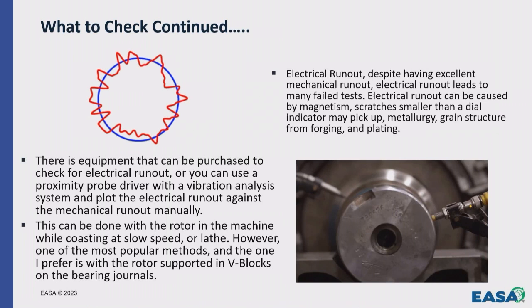And you can get all kinds of unusual patterns. If you have a lot of Gauss, you may have more of an elliptical pattern in the red. So despite having excellent mechanical, which we were, you know, two tenths, I mean, excellent mechanical runout, we had 3 mils of electrical runout. So there was no way we could pass that customer spec that was 1.5 on that initial motor that I was talking about. There's equipment you can buy commercially available for this, and then there is also, you can plot it out with your standard vibration analyzer.